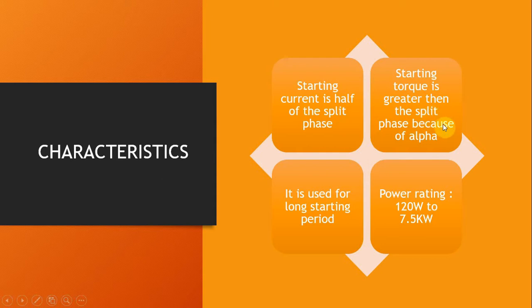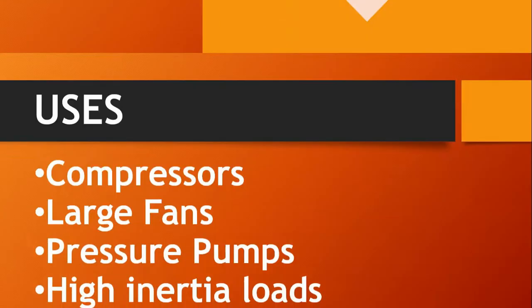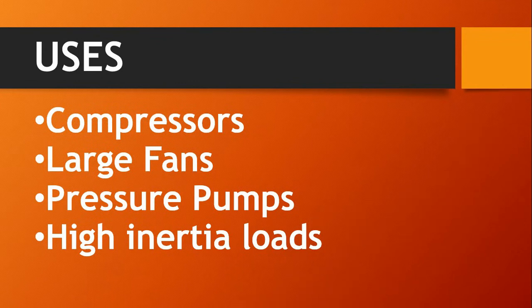The starting torque is greater than the split phase because the alpha is 80 degrees, compared to 25 degrees in the split phase case, which produces a greater starting torque. It is used for machines with long starting periods. The power rating is 120 watts to 7.5 kilowatts. Such motors are used in compressors, large fans, pressure pumps, or other high inertia loads.